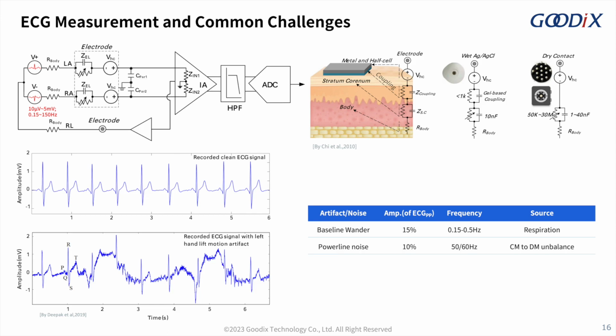Power line noise. The test subject is exposed to radiation from the surrounding power grid, which can couple power frequency common mode interference with a voltage of several volts to a dozen volts. The challenge of measuring ECG on a watch lies in the fact that the electrodes are on the wrist and finger respectively, and the contact impedance and parasitic capacitance of the electrodes will differ, transforming common mode interference to differential signal and forming strong interference.